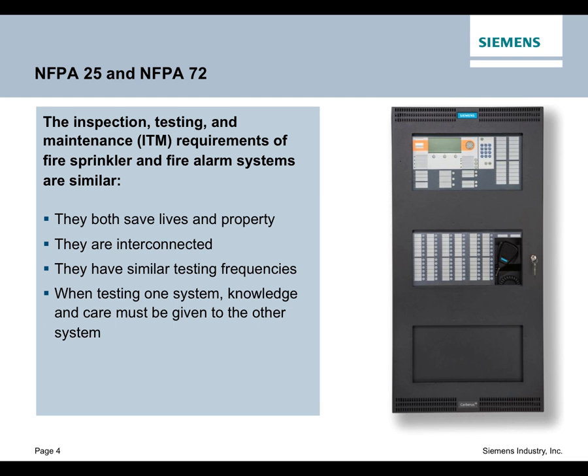We could maybe do without air conditioning for a little while. And sometimes we can do without escalators and other important building systems. But the fire sprinklers and the fire alarm systems need to rise to the top of the list as far as importance goes as we march forward. And the fact of the matter is, as many of you are aware, these things are interconnected. The fire sprinkler system piping throughout the building has many electronic connections that tie back into the fire alarm system so that they are connected physically. And they have similar testing frequencies.